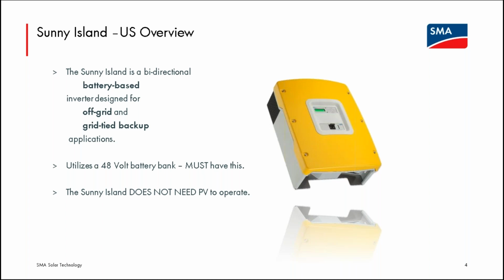If there is PV in the microgrid, SMA is an advocate of AC coupling, and we'll talk about that in a few slides. But generally, we would recommend having a PV system with an inverter, having the AC output of that PV system meet on the same loads panel, which will be called the protected loads panel, as the AC output of the Sunny Island. So that is a very quick summary of what AC coupling is.